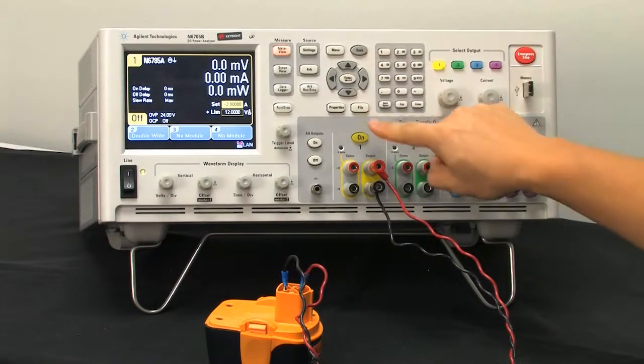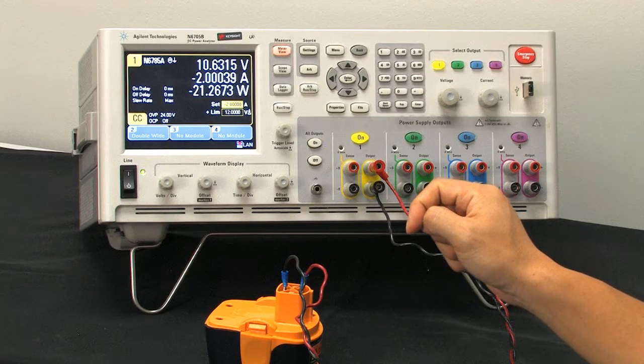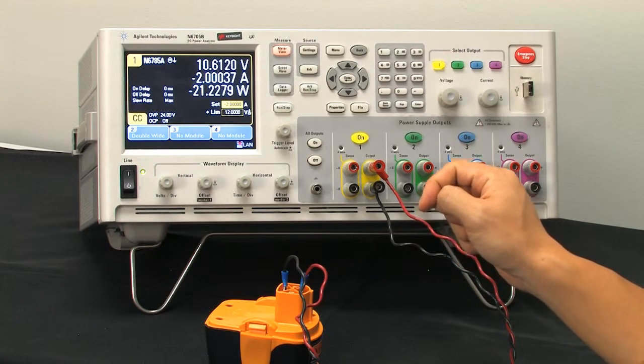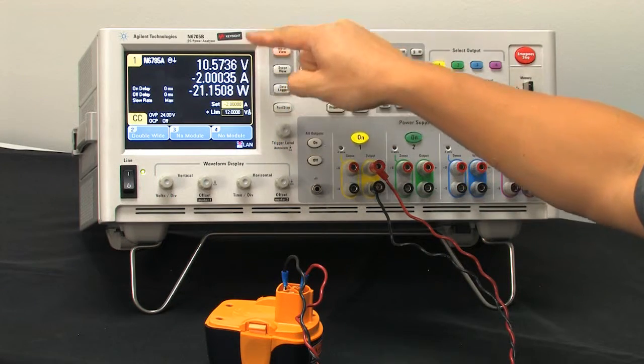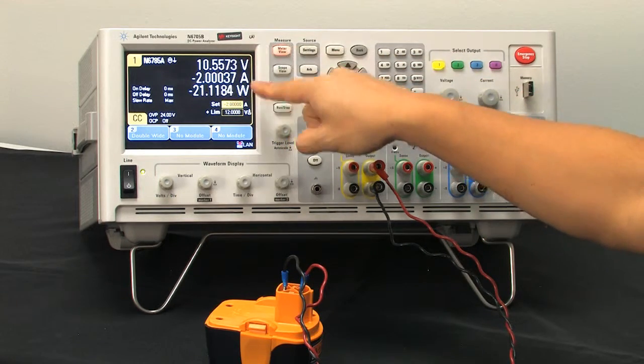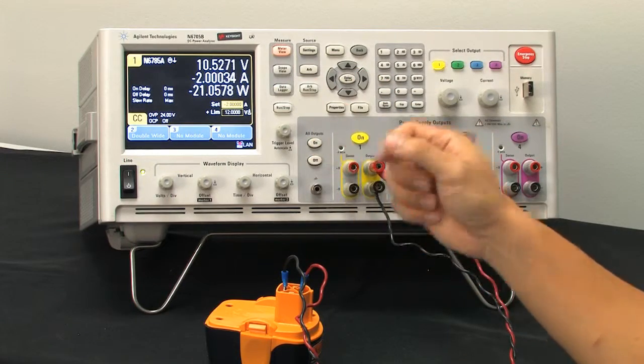Let's go back to our meter view and we're going to enable the output. So right away you'll see that the voltage value is dropping ever so slightly. It's going down and it will keep going down for a really really long time. And this indicates the discharge of the battery.